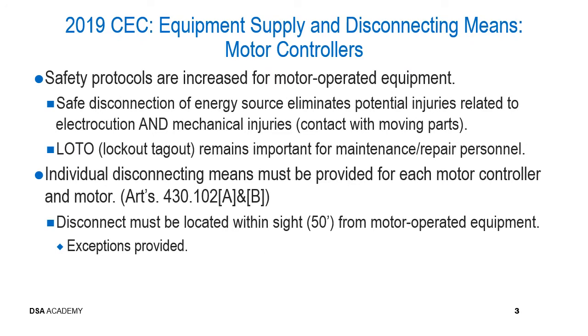Let's start by talking about some of the safety protocols that need to be increased due to the fact that these pieces of equipment that we're discussing are motor operated. The safe disconnection of the energy source eliminates potential injuries related to electrocution, obviously, but specific to motors and motor controllers, mechanical injuries are also a potential injury, due to the fact that with motor operated equipment you've got moving parts, and contact with moving parts is a potential mechanical injury that is unique to motor operated equipment. Obviously, lockout tagout protocols remain certainly important for maintenance and repair personnel and must be employed even during the construction phase when the equipment is energized.